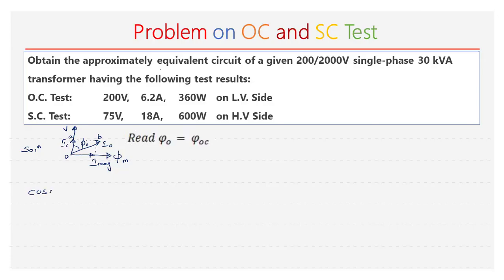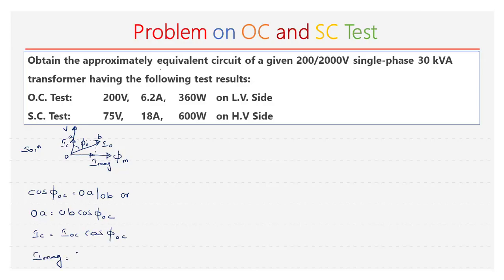From the triangle OAB, we can write cos φ0 is equal to adjacent by hypotenuse, that is OA divided by OB. OA is equal to OB into cos φOC, where OA is nothing but Ic. So Ic is equal to IOC into cos φOC. Similarly, the magnetizing current is given by Im is equal to IOC into sin φOC.